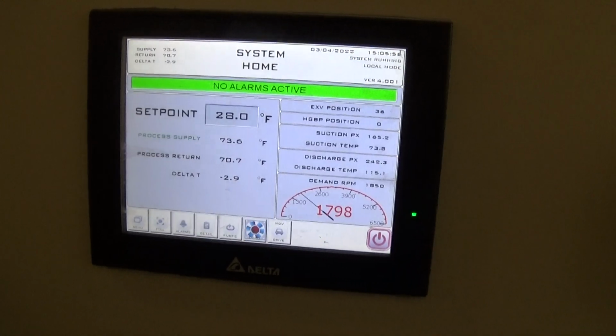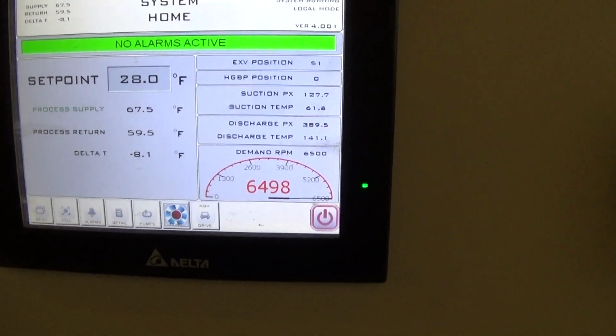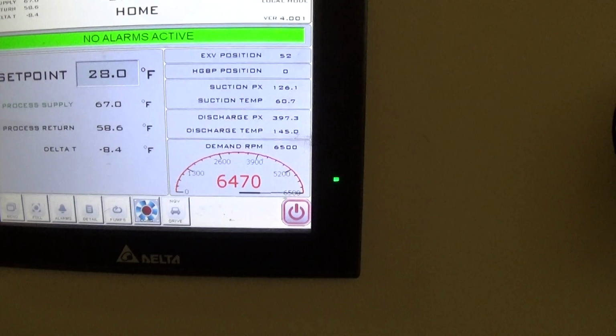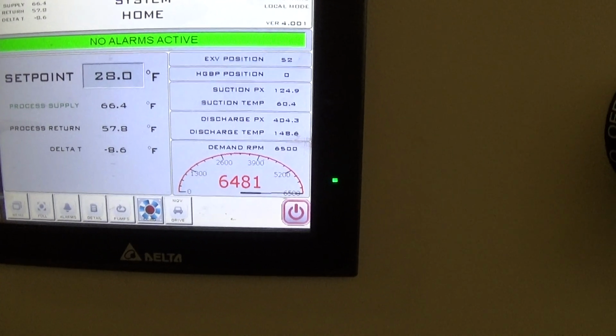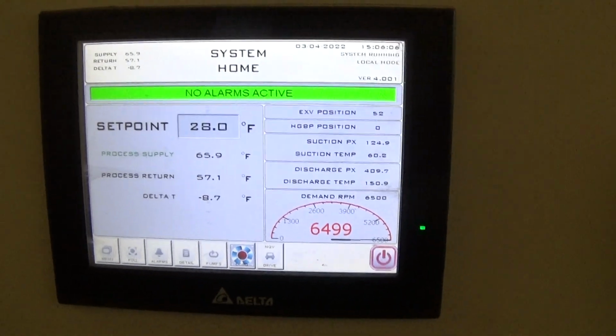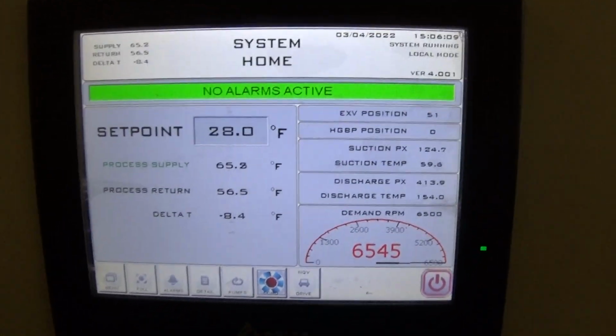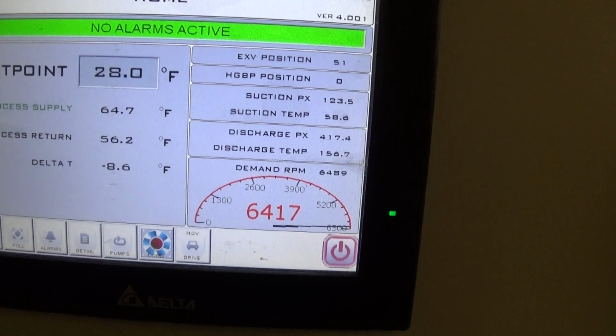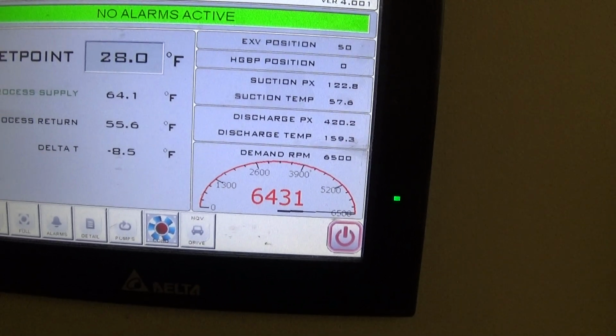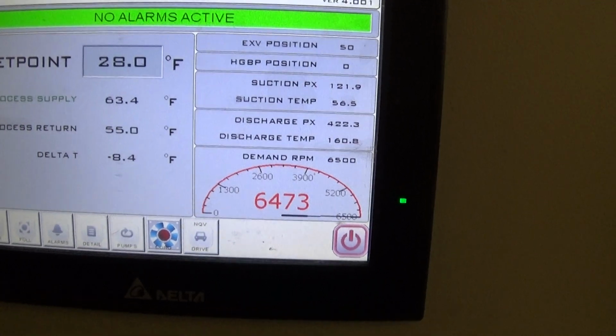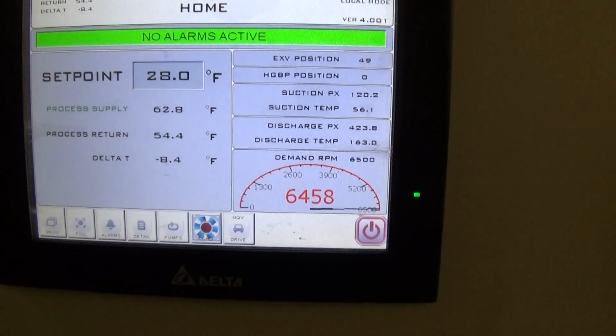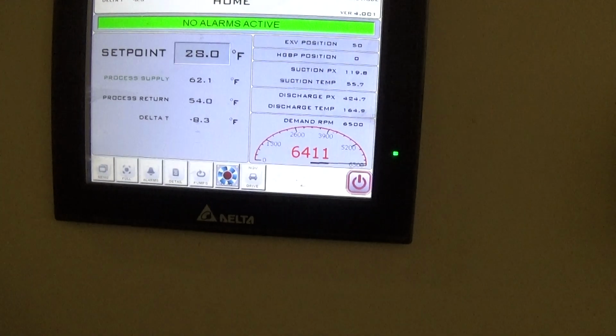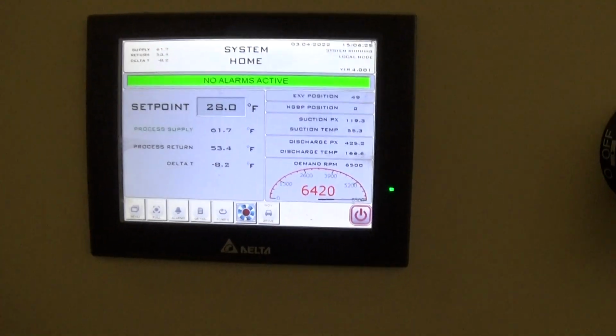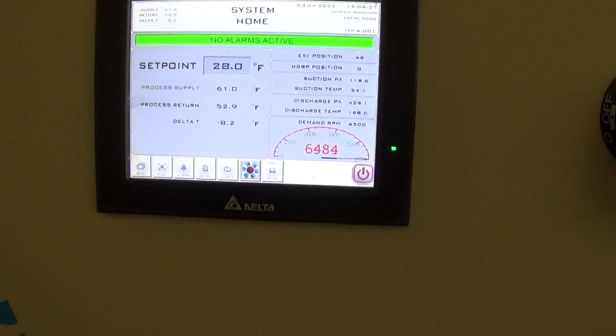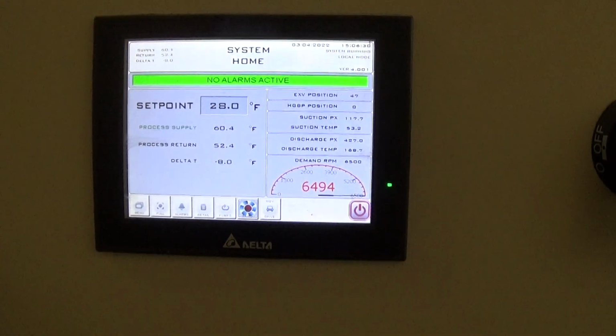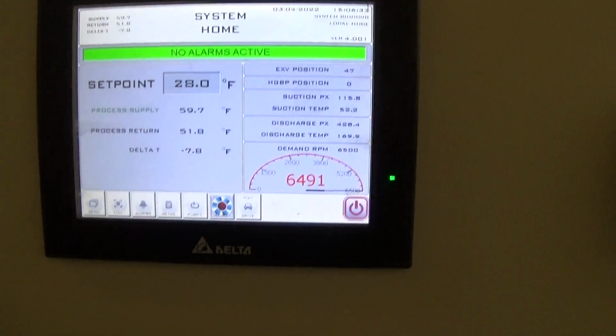We'll go back to the home screen. And you can see right now I got a load. We plugged in our air handler. So now it's running at the full 6,500 RPMs while we're dropping temperature down. Right now our process supply temperature, you can see, is 65-ish, and the return is 56-ish, delta T of 8. That's actually a pretty good delta T for our test parameters right now. It'll probably drop the temperature pretty quickly. What else we got here for some screens?